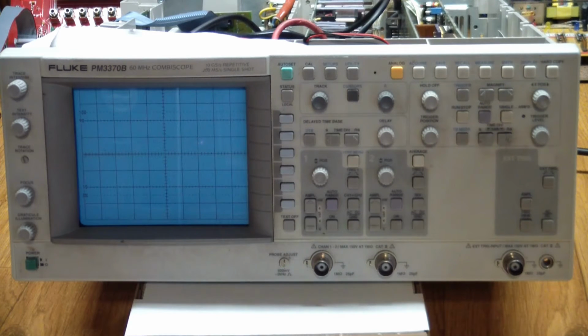I plugged the supply board back in and turned on the instrument and made sure that all of the voltages generated on the power supply, other than the high voltages, were good. I checked the ripple on them. It was within spec. So the low voltage on the power supply was all good. And after that I proceeded to fix the HV side. And now you're all burning to hear what the bad thing was.